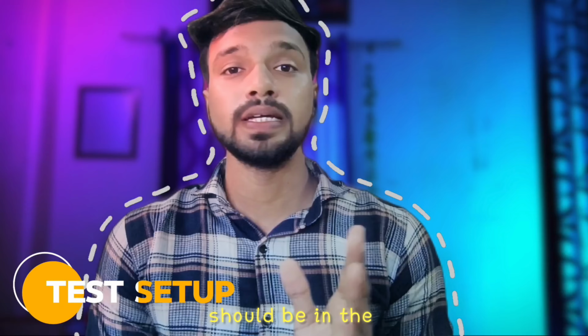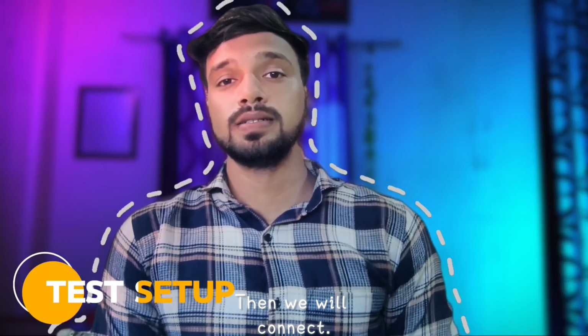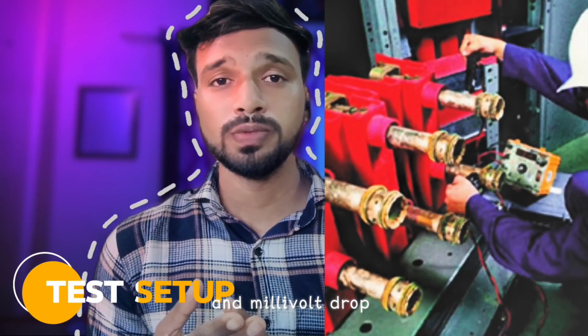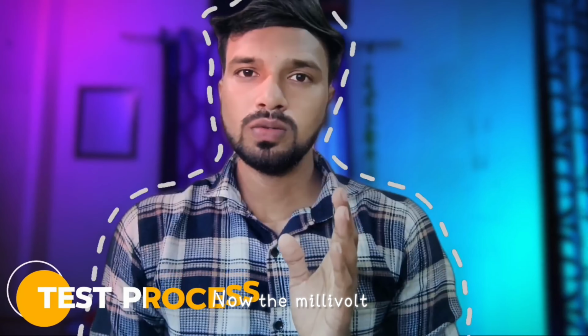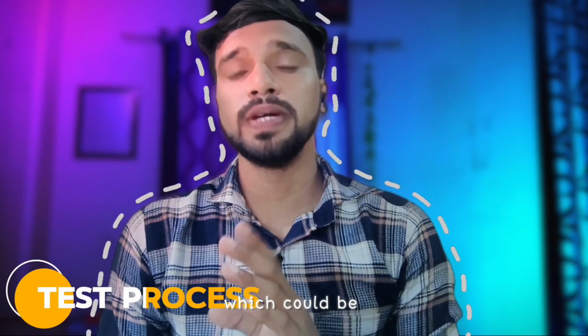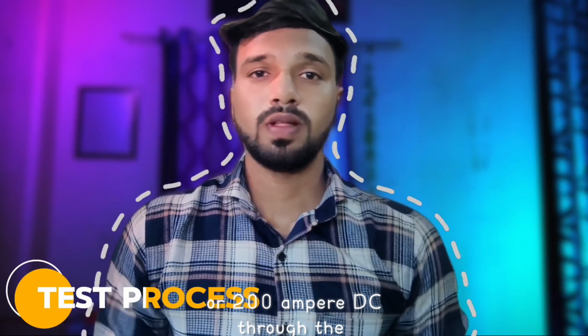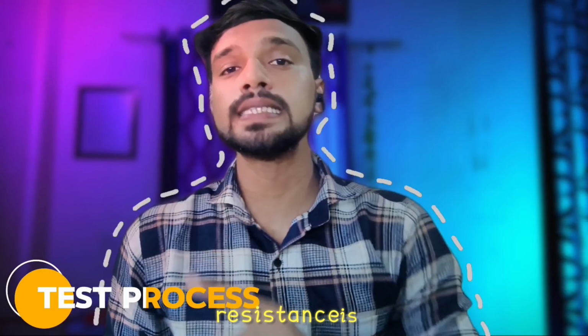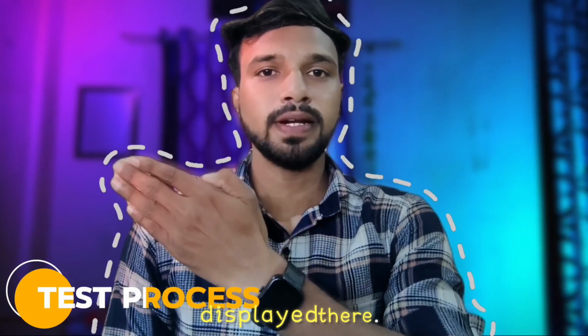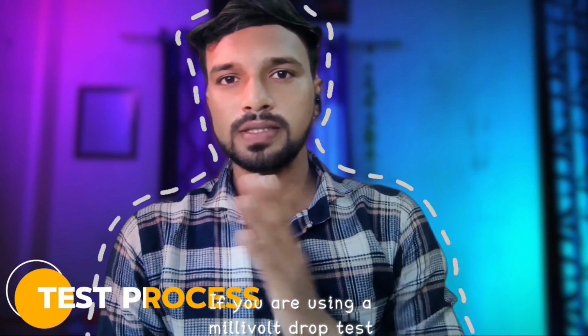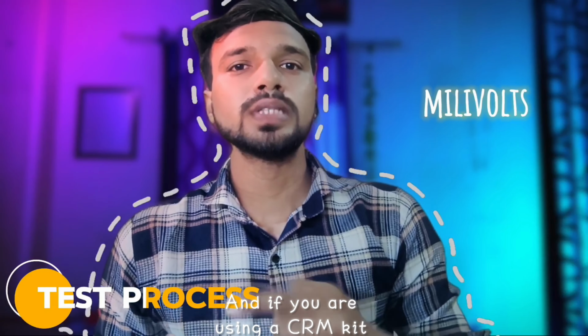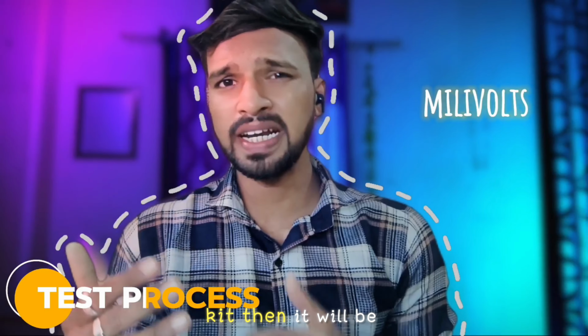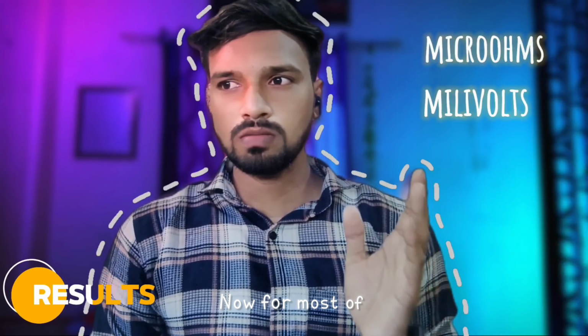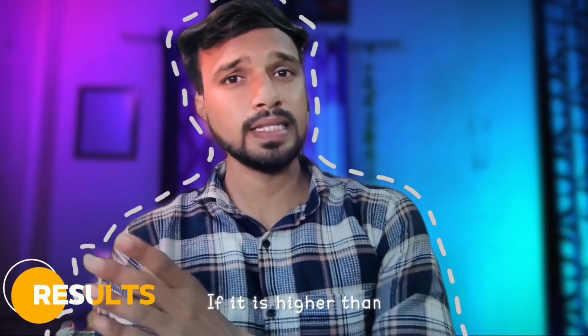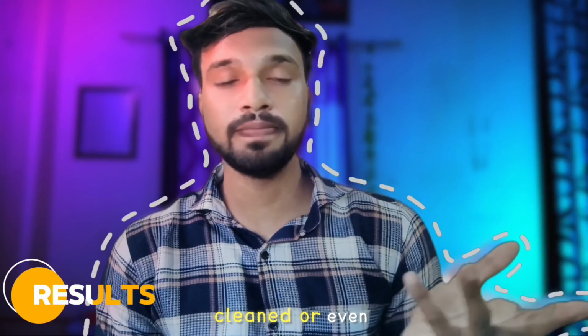To run this test, the breaker should be in the closed condition. Then we will connect the probes, which are the current and millivolt drop probes, to the breaker's incoming and outgoing terminals. Now the millivolt drop trolley will send a current, which could be 100 or 200 ampere DC, through the contacts of the circuit breaker, and it will measure how much resistance is there, and that will be displayed. If you are using a millivolt drop test trolley, then it will be shown in millivolt drop, and if you are using a CRM kit, contact resistance measurement kit, then it will be directly shown in micro-ohm. For most breakers, the contact resistance should be very low, typically less than 100 micro-ohms. If it is higher than this, then the contacts might need to be cleaned or even replaced.